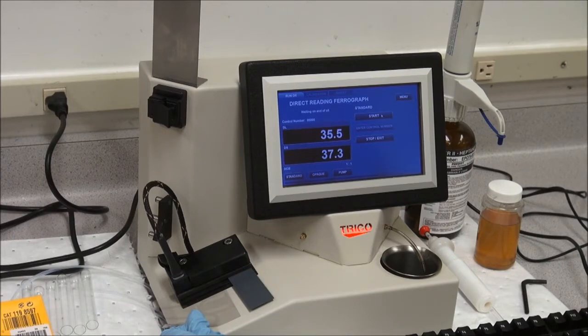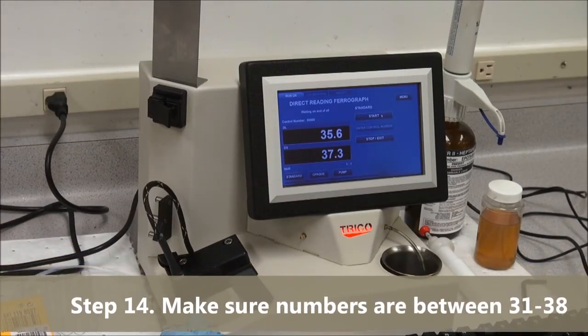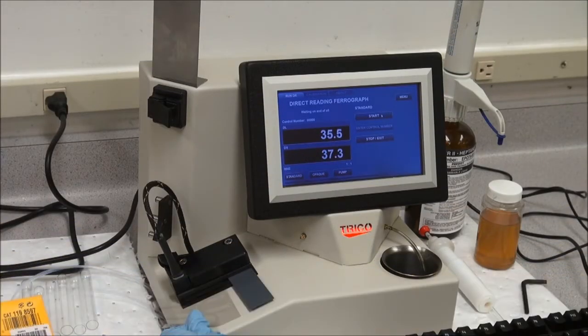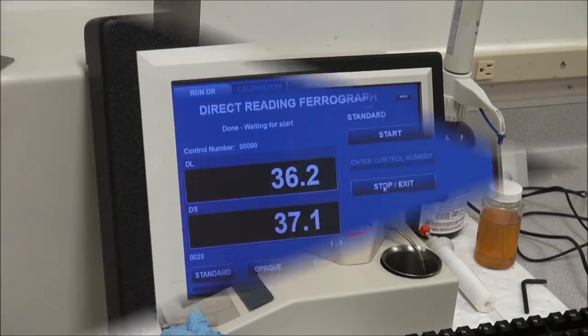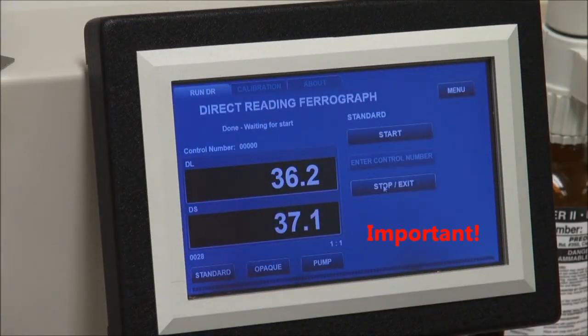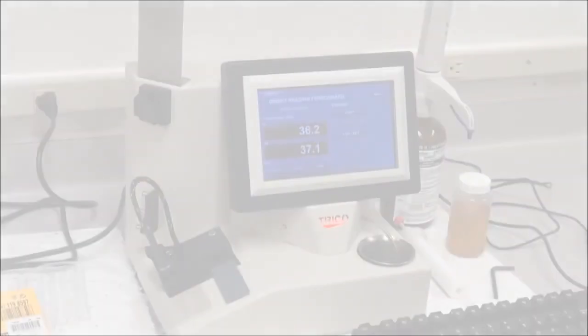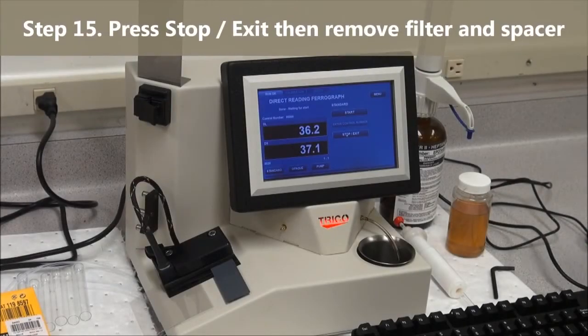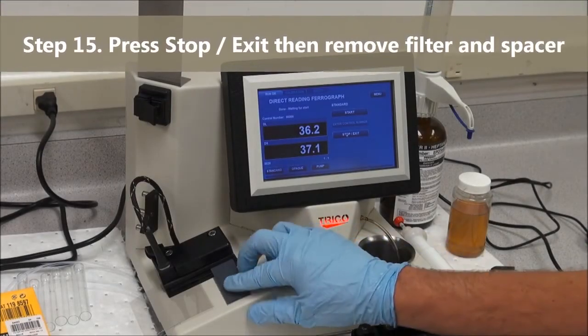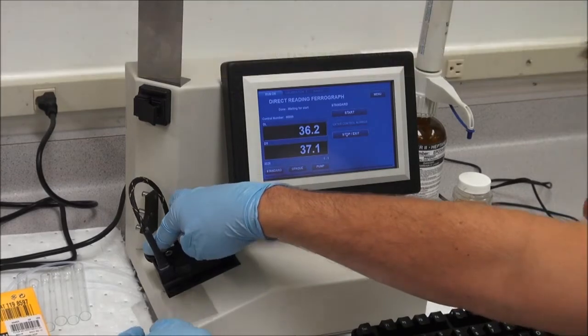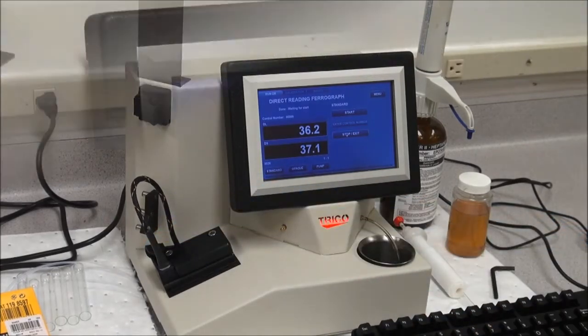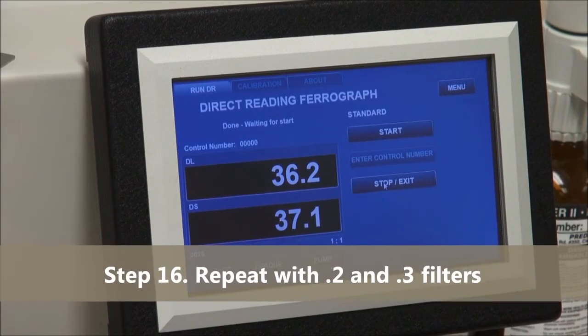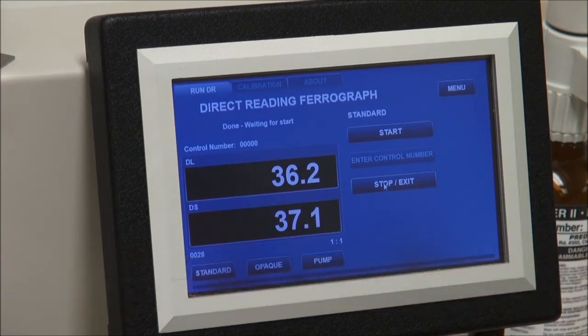Assure that they fall between the 31 and 38 range stated in the instruction manual. If they do not fall within this range, the magnetic block needs to be readjusted and the calibration needs to be redone. Hit stop exit as your test is completed. Remove the spacer, remove the 0.1 filter. Repeat this process with 0.2 and 0.3 density filters.